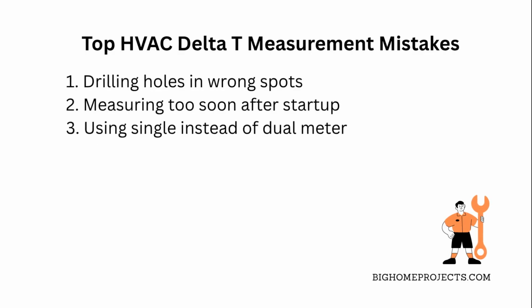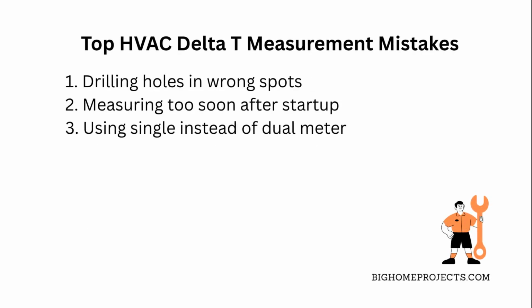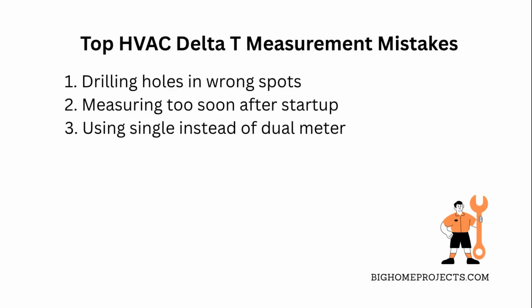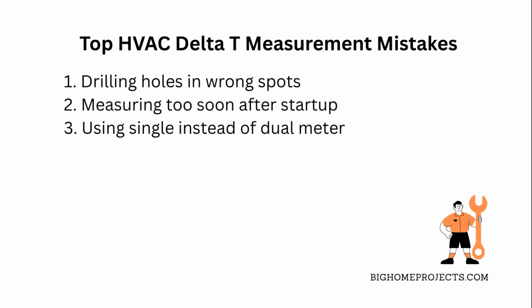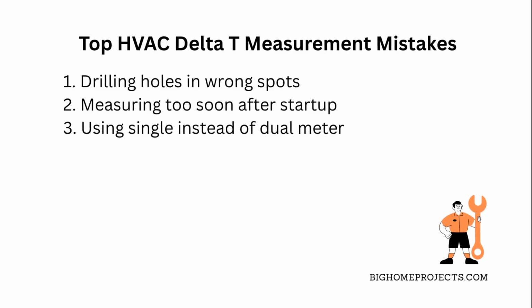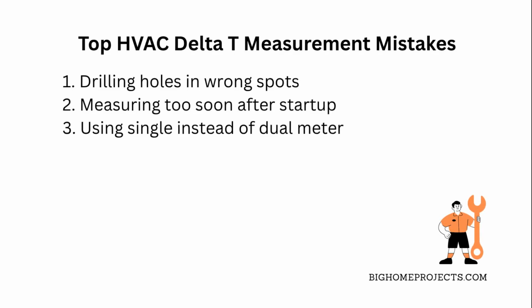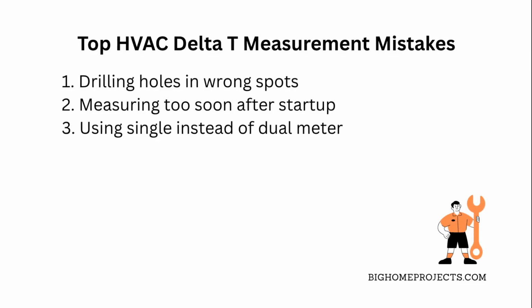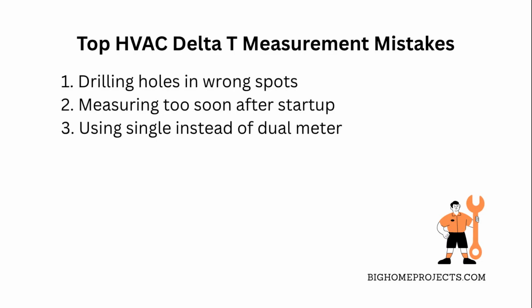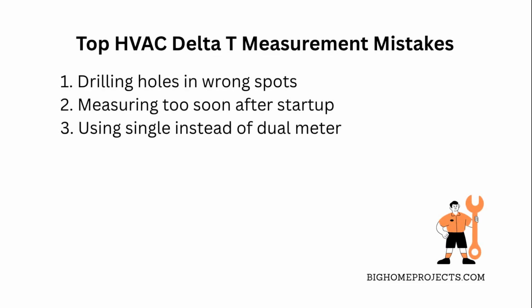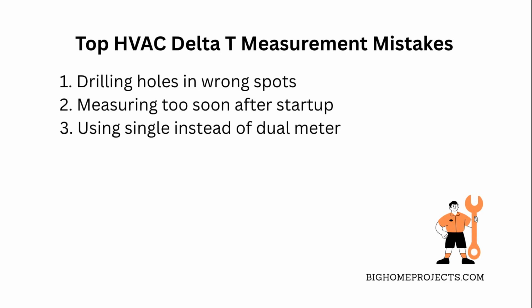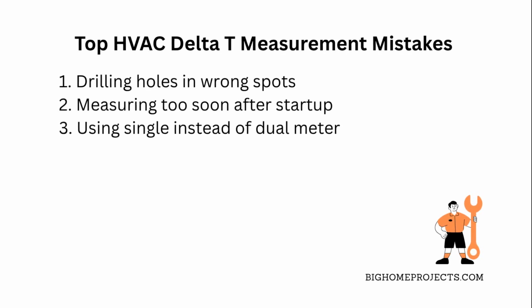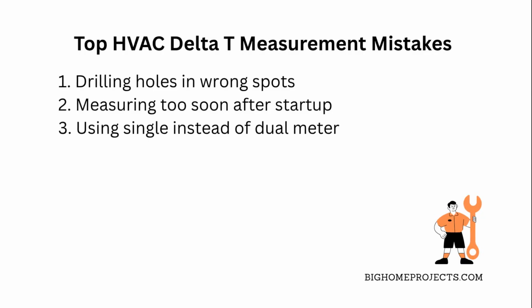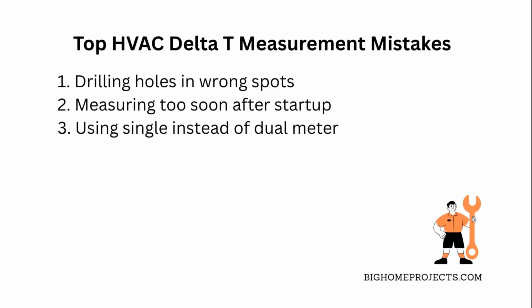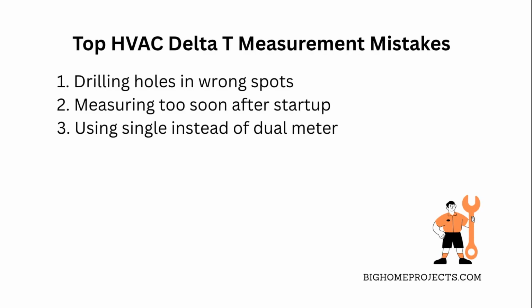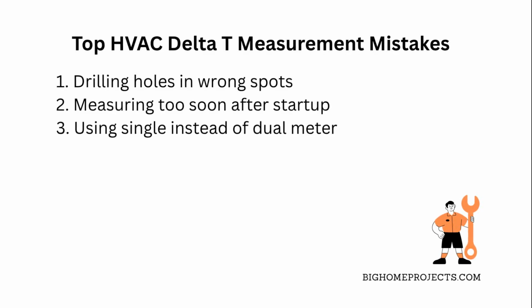One of the biggest mistakes people make when measuring HVAC Delta T involves drilling holes in the wrong spots, which gives inaccurate temperature readings. Fix that by choosing locations away from bends or dampers for more consistent airflow. Another issue is not letting the system run long enough before measuring. If you check temperatures too soon, your Delta T won't be reliable, so always wait at least 5 minutes before taking readings. Lastly, using a single temperature meter instead of a dual probe setup can cause errors and waste time. Investing in a dual temp meter set to differential mode makes everything simpler and way more precise.